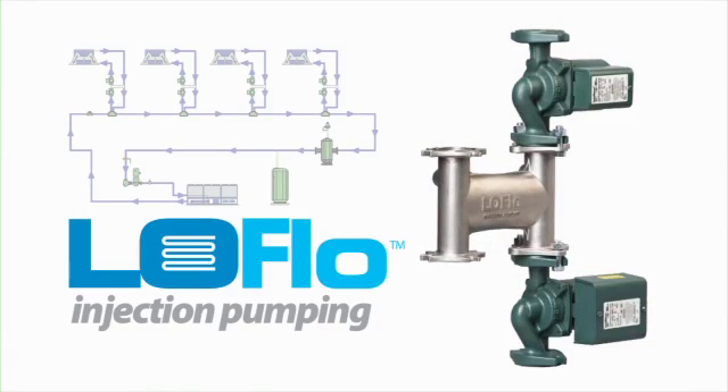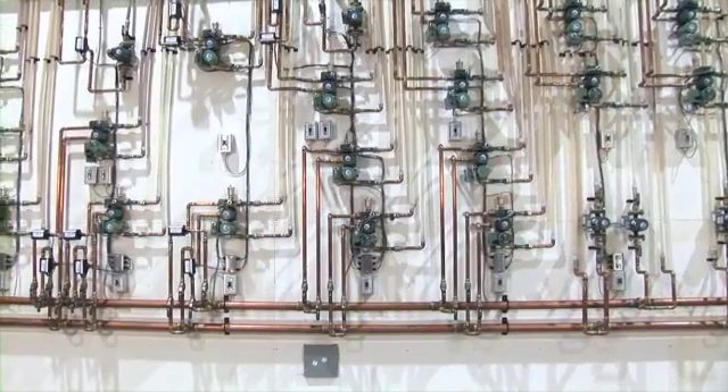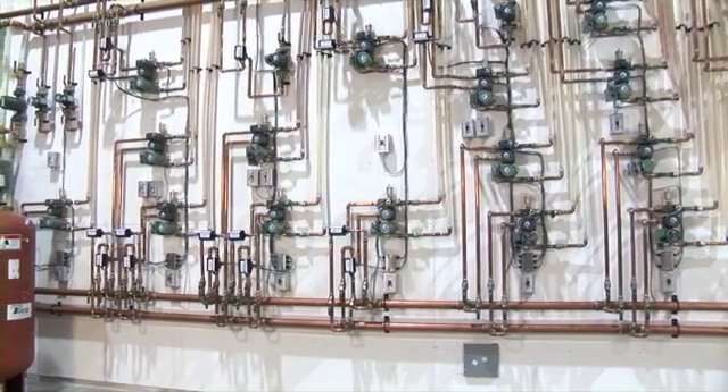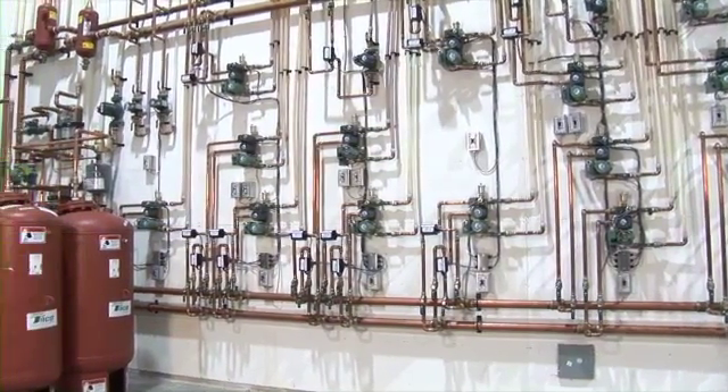The TACO LoFlo system is a single-pipe low-temperature water system that circulates chilled water and mixes it to the proper temperature at the point of use. It uses the same time-tested technology of injection pumps, used successfully in radiant heating systems for many years.